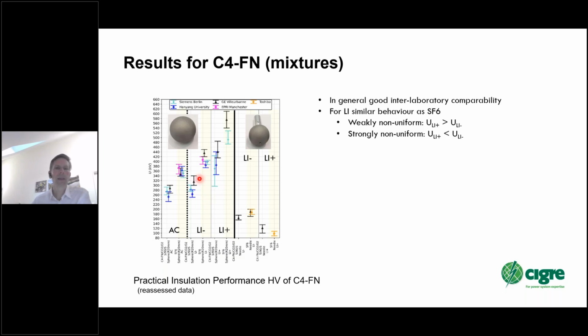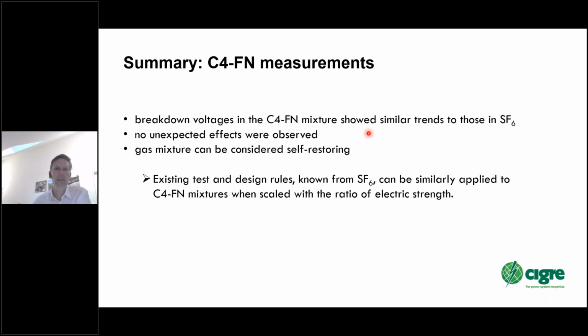So that means under the weakly non-uniform configuration, in SF6 but also in the new gas, the positive lightning impulse breakdown strength is higher than the negative. But for the strongly non-uniform, it's the opposite. There, the positive is the critical one. With this information, you can still work on the most critical part, and you don't have to always perform both tests. The behavior is very much like we are used to from SF6. And with this, the dimensioning and the performance assessment can go as we know it from the SF6 developments.